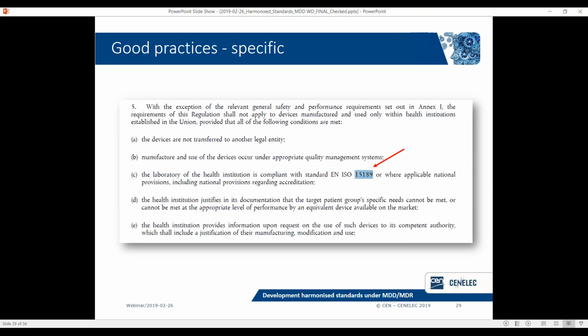Now, the question would be, all right, but for us, the important thing is not the exception, but the main, let's say, setting, when we are talking about IVDs which are subject to regulation, so not in-house manufactured ones. And then our reply would be, we have a problem here, because according to Article 8 of the MDR or the corresponding article of the IVDR, a standard cannot be addressed to a user, because for normal IVDs, a lab will not be a manufacturer. It will be someone else. So I think that this example reflects a little bit of the philosophy of the addressee and of the, let's say, voluntary use of a standard as an instrument which can be used in order to comply with general safety and performance requirements.